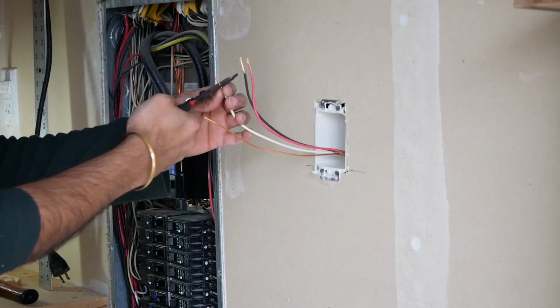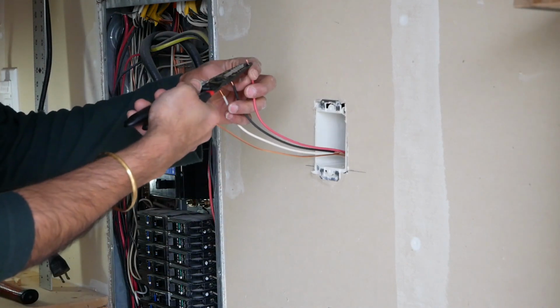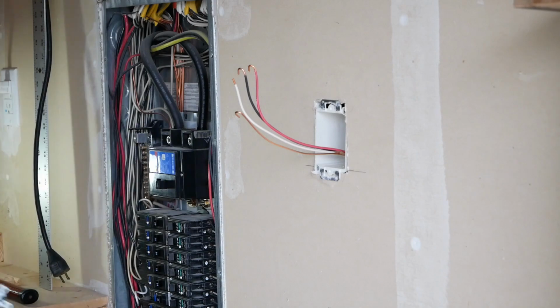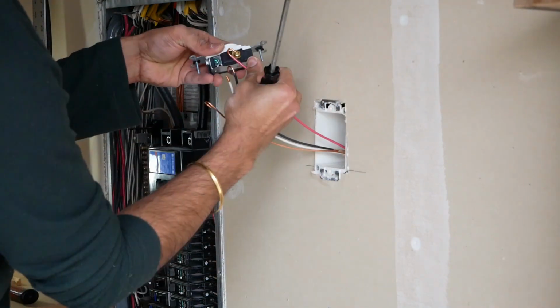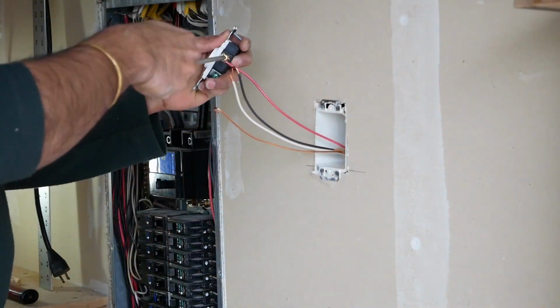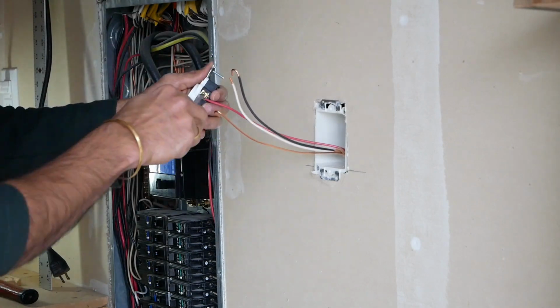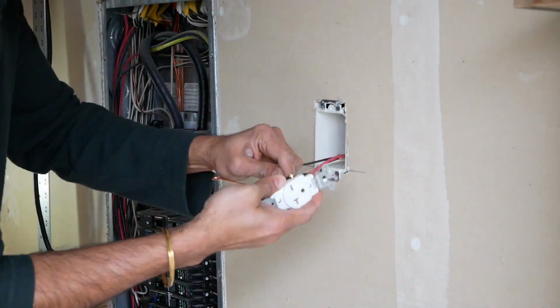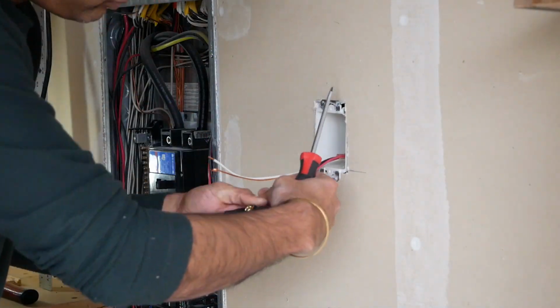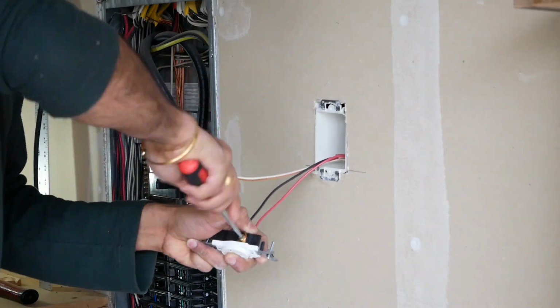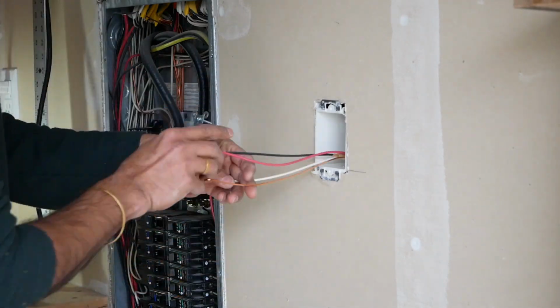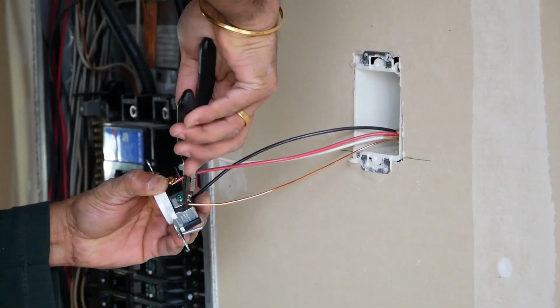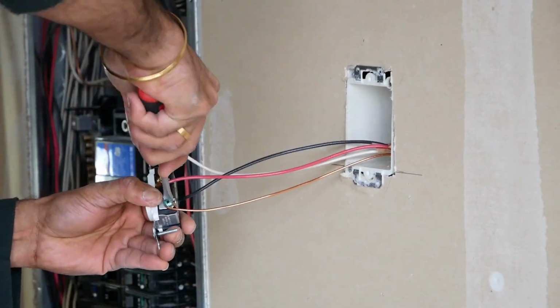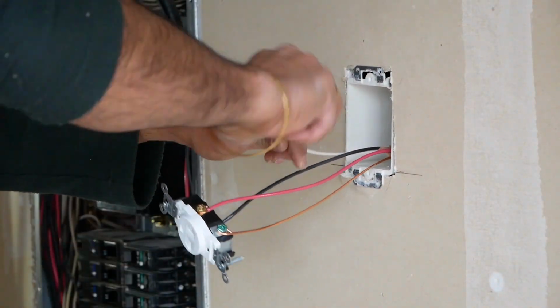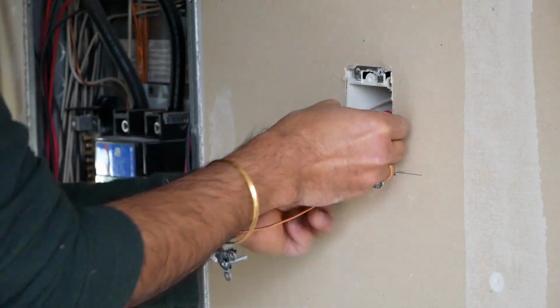In order to install the wire, we strip the top end, make a U and then connect it securely to the outlet. For a 240 volt outlet, it doesn't matter which side the red or the black wire goes. Both are hot, so it can go either side. The ground is the one you will need to make sure that you connect properly to the green screw. In this case, the neutral is unused, so we put a wire nut on top of it.